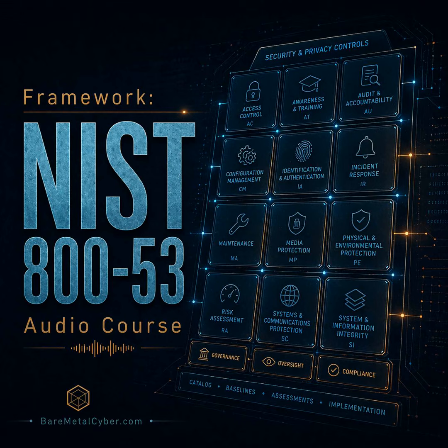Oversight extends beyond internal teams to third-party qualifications and artifacts. External service providers must demonstrate their competence through certifications, background checks, and adherence to approved processes. Oversight records might include copies of vendor training credentials, non-disclosure agreements, and service reports. For example, if a contracted specialist updates control system firmware, their report should include technician identity, training evidence, and validation steps performed. Collecting and reviewing these artifacts prevents blind reliance on vendor promises. It also enforces parity. Outside partners meet the same standards as internal staff. Oversight documentation converts dependency into documented assurance.